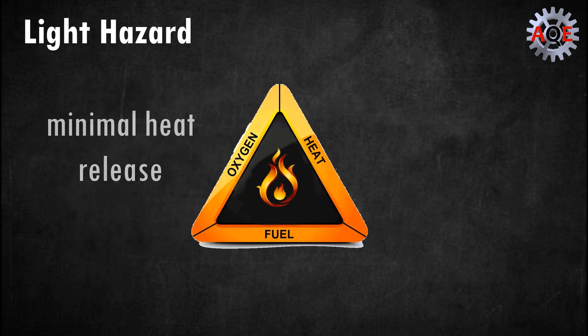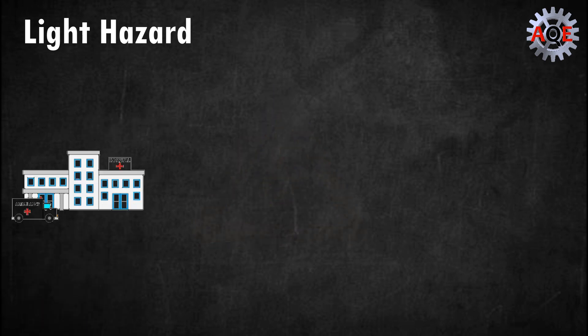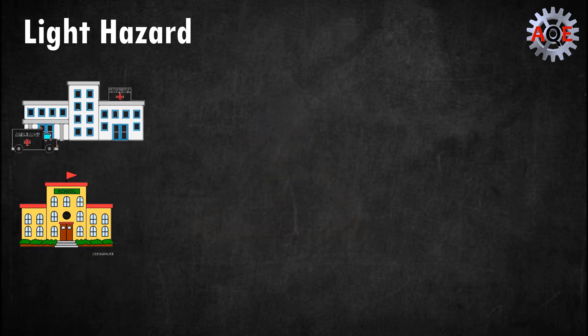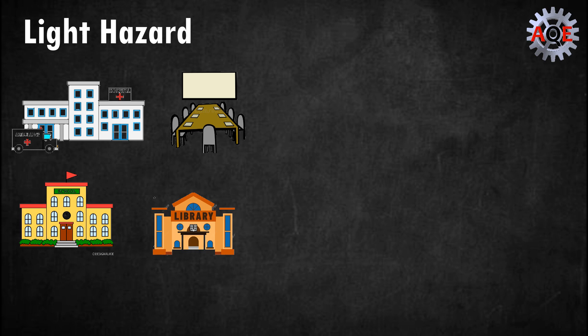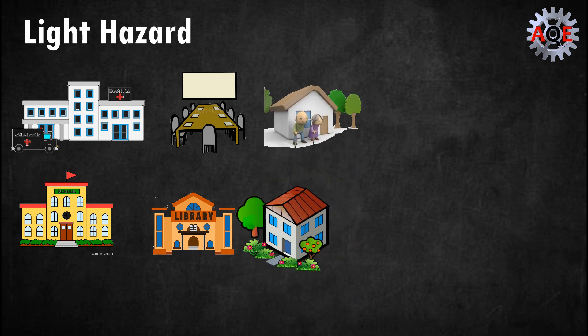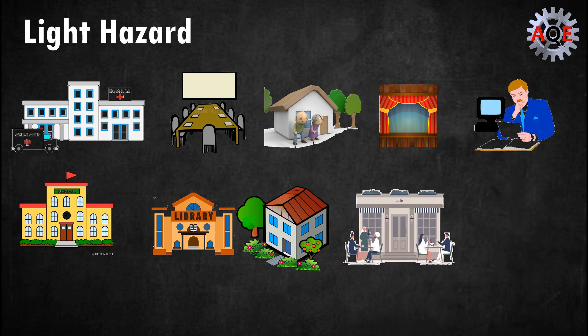Some of the light hazard areas may consist of hospitals, educational institutions, meeting rooms, libraries aside from massive stack rooms, nursing homes, residential areas, auditoriums and theaters aside from prosceniums and stages, seating areas in restaurants, offices, and data processing.